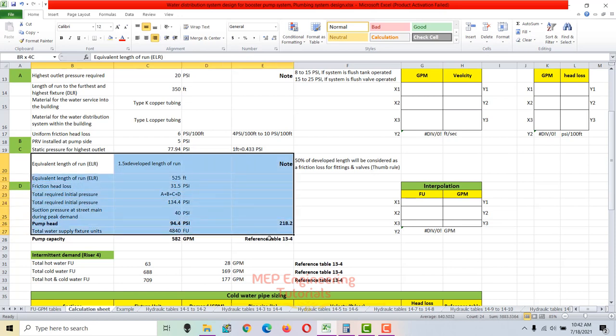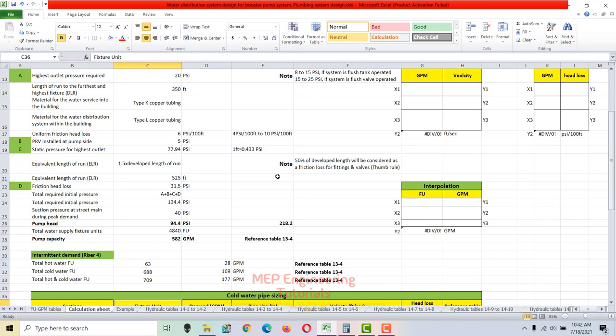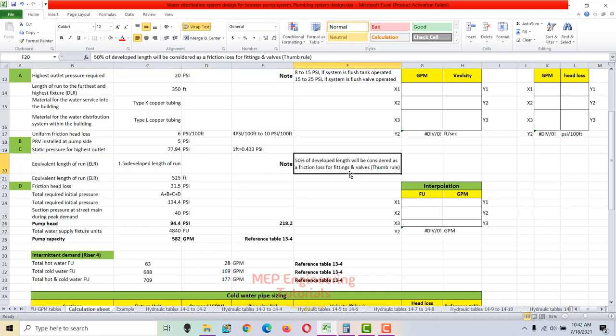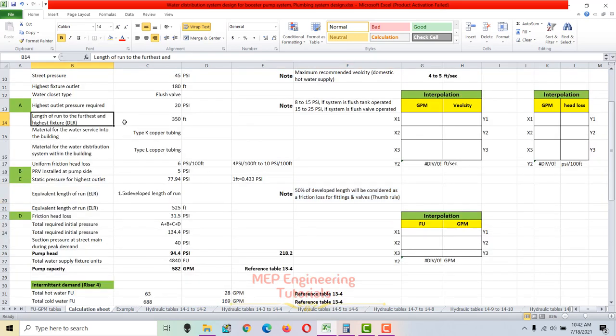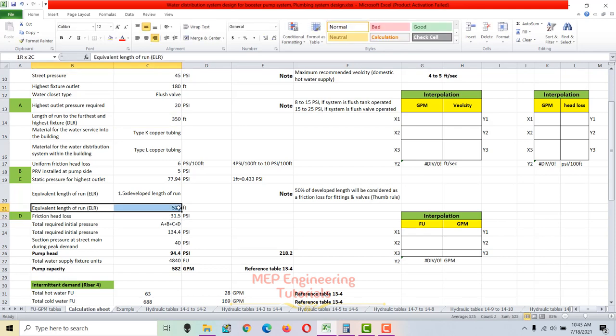The equivalent length of run is the straight piping length plus the equivalent length for valves and fittings. Since we don't yet know the pipe sizes, we use the thumb rule: add 50% of the developed length as the friction allowance for fittings and valves. So the equivalent length of run is 350 × 1.5 = 525 feet.